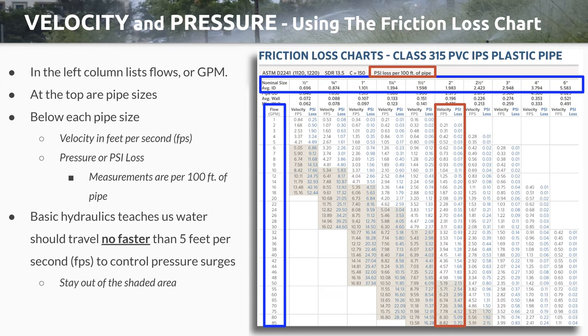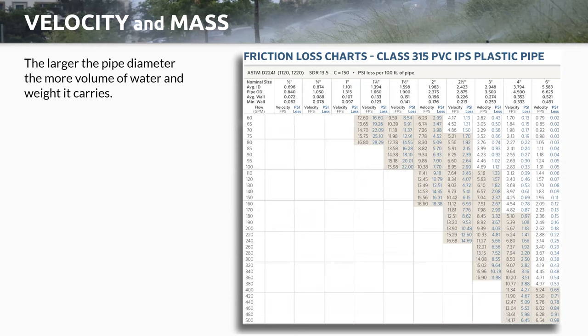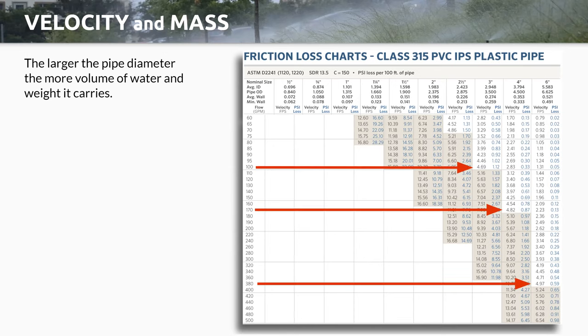Basic hydraulics: any of you that have been through IA classes or other irrigation design classes know that water needs to travel no faster than five feet per second. We'll talk about that — you want to stay out of the shaded areas. When you get into larger systems and you're using larger diameter pipe, the larger the pipe diameter, the more volume of water and the more weight it carries. So when you're getting into three-inch, four-inch, six-inch, even 12-inch sizes, you need to be aware that you have a lot of force in these pipe systems with the amount of water going through your irrigation system.